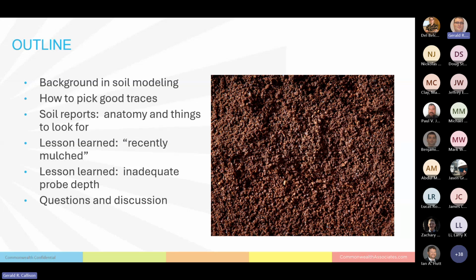In my role doing grounding for Commonwealth projects, sometimes I have to send out a very unhappy message that the soil measurements we had planned on, that we'd been provided to do our grounding design based off of, are not good. That's definitely not a message you want to get when you're expecting a grounding design in a matter of a few weeks and find out you have to go back and retake measurements. So if anything, I'm really hoping this talk today can educate people on how to take good measurements for grounding, and how to avoid finding out at the last minute that you need to retake measurements for soil resistivity for grounding.